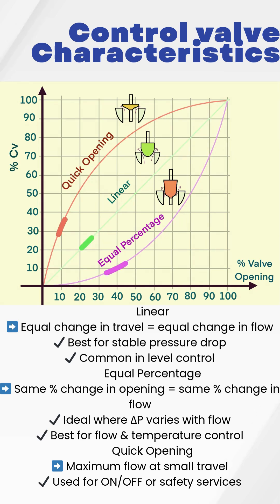There are three main characteristics. Linear characteristic gives equal flow change for equal valve travel. It works best for level control and systems with stable pressure drop.